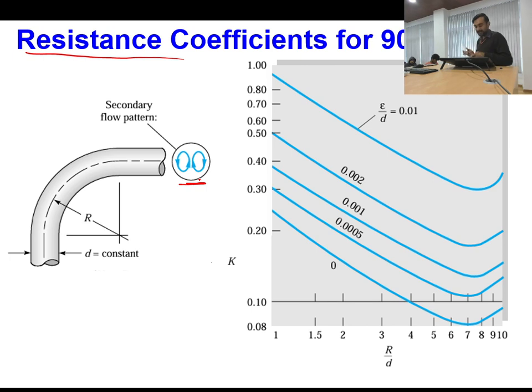Okay, so it means that whenever I use the loss coefficient from this diagram, then I have to also use additional loss because of the flow along the length of the bend, because a bend can have significant length. So say along the axis, this curve has length LB. So I have to also use f LB V square by 2g to quantify the major loss, plus whatever other secondary losses come because of the presence of the bend, that I will quantify with K V square by 2g.